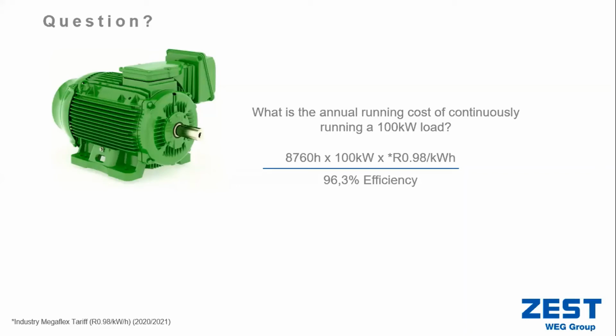2020-2021. And then I went to look at this motor and say, well, this is an IE4 motor, so the rating on the efficiency of this motor was 96.3. And I'm not sure if anybody wants to guess, but after running this motor for exactly 1 year, that would be the cost that we'll have to pay the utility company to run one motor of 100 kilowatt power delivered on the shaft for 1 year.